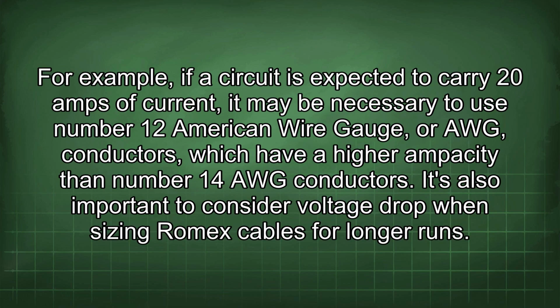For example, if a circuit is expected to carry 20 amps of current, it may be necessary to use number 12 American wire gauge, or AWG, conductors, which have a higher ampacity than number 14 AWG conductors.